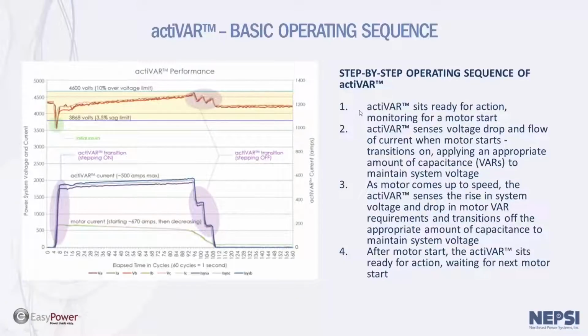This slide here shows the performance of the actiVAR. You can see on the top here we have the system voltage. The nominal system voltage here is 4160 volt. At the starting point, the system voltage is around 4160 volts, and as the motor starts, there is a brief dip in voltage. At that point in time, the actiVAR will push phase on the thyristors, which will then push out the current and supply reactive power locally. And you can see during the starting period, the voltage will rise to a point where the reactive power will start to drop off here, and the actiVAR output current will start to stage off.